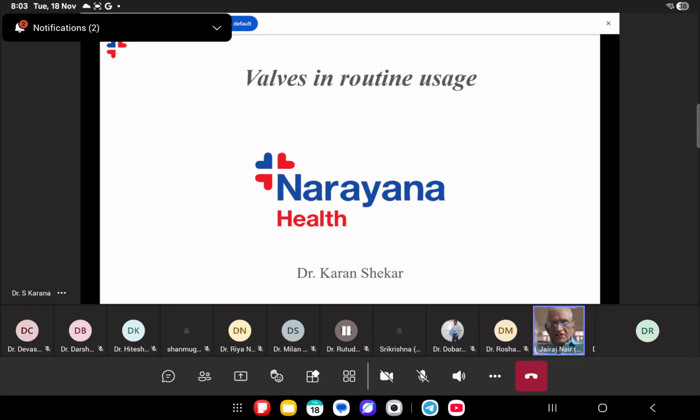What is the disc in the Chitra valve? Sir, it is a polytetraphthalate. That's not the correct thing. I expected better from you. Ultra high molecular weight polyethylene. Yes, sir, it's a polyethylene.